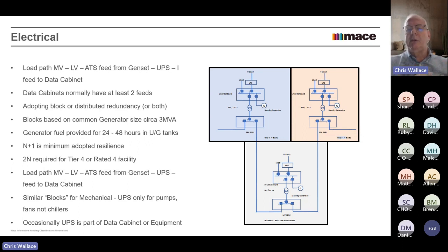So again, what you'd typically do is you'd have the red and the blue feed, and then what you have there at the bottom is another block, and that block would be a redundant block. So basically you'd say, right, I've got N, which might be two, and the plus one is the redundant block here. That redundant block might be one redundant block per hall, or it might be one redundant block which would serve all the red and blue units. And this is the difference between block redundancy and distributed redundancy, and in some cases you might go for a combination of both. And as I said, the blocks are typically 2.5 to 3 MVA generator size.